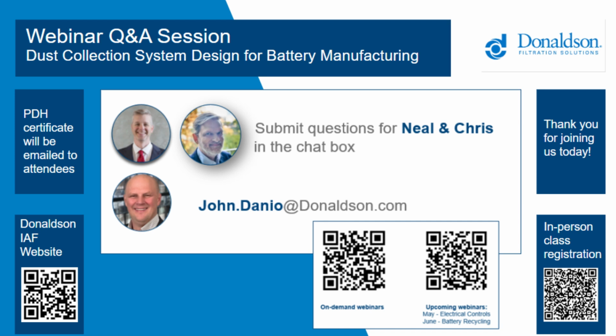That's something that needs to be managed by the maintenance team and monitored. It's very common that it comes set at 4 inches for a high, 2 inches for a low. Once it exceeds that 4 inches, it's very common that they forget to go in and change the high and low set points. These are designed to run up to 6 inches of differential pressure on the filters. So that's a common issue we see. Another common issue is the pulse valves themselves. It's a wear part.